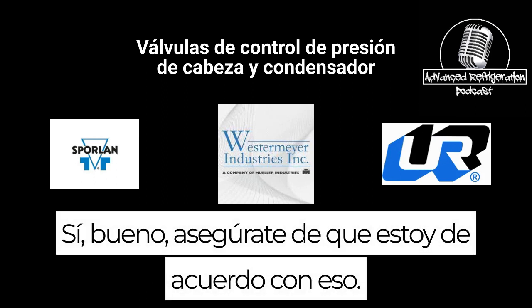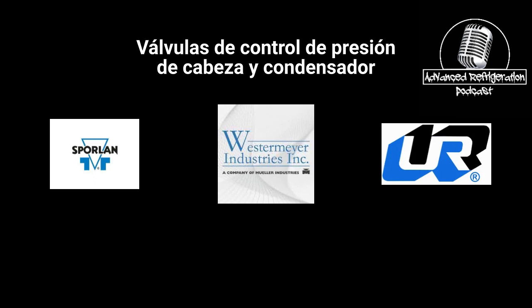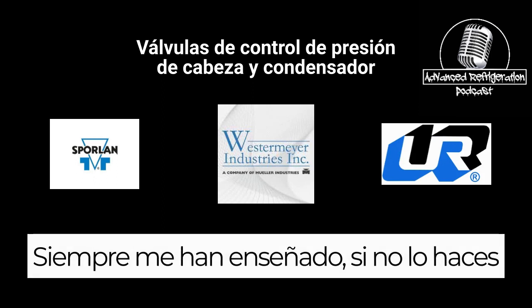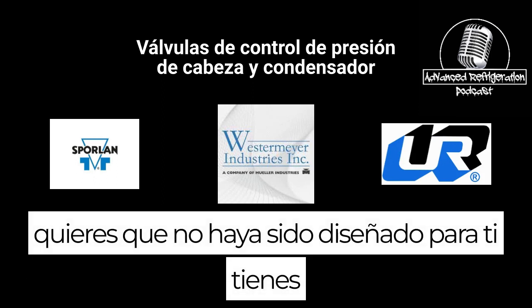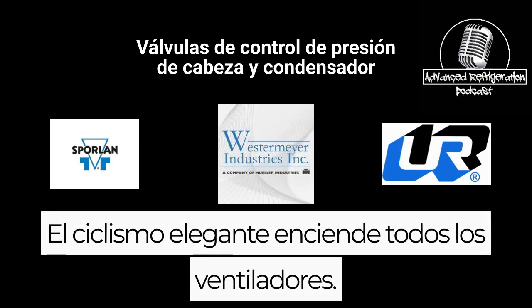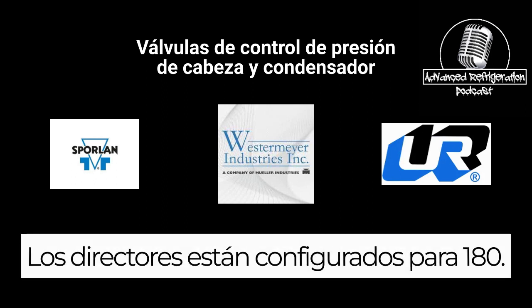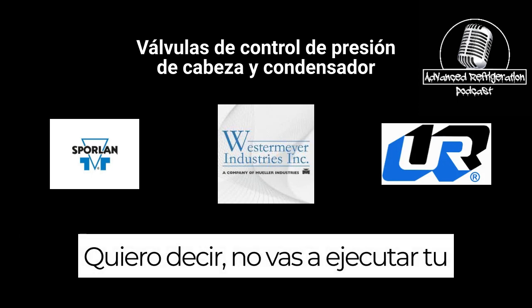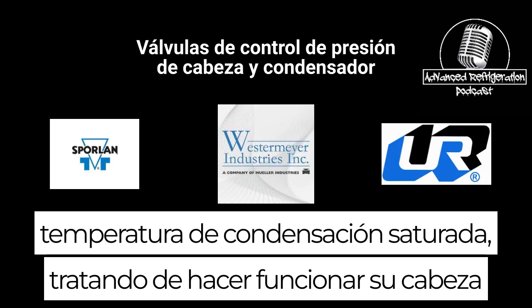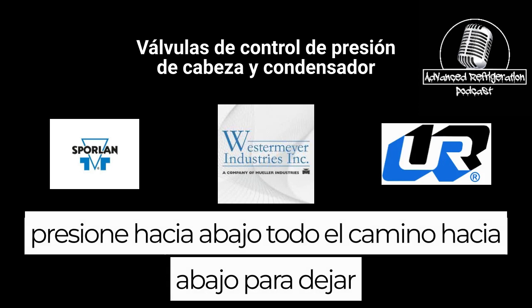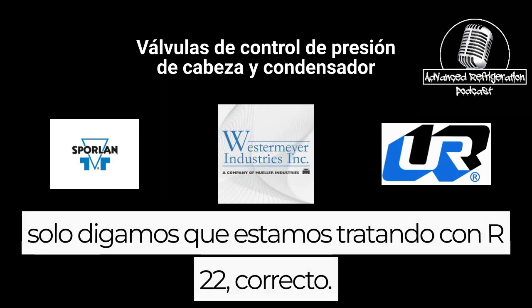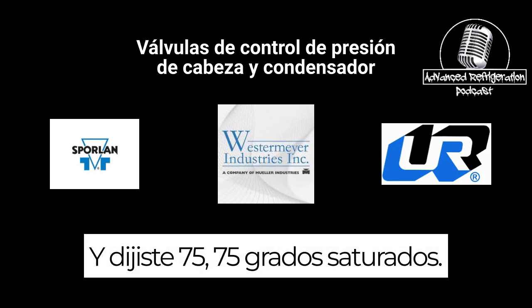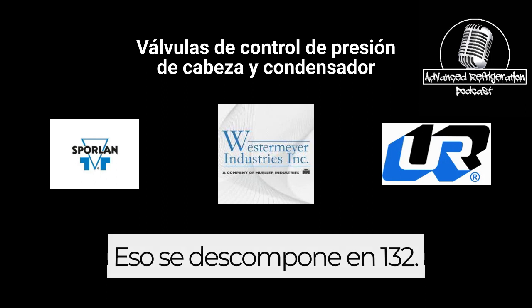Yeah, I agree with that. I've always been taught that you don't want a head pressure that wasn't designed for. If you have fan cycling switches on every single fan motor, let's just say we're dealing with a Hussmann unit, we have four fans, right? The headmasters happen to be set for 180. You're not going to run your saturated condensing temperature trying to bring your head pressure all the way down. Let's just say we're dealing with R22, right? And you said 75 degrees saturated, that brings it down to 132.